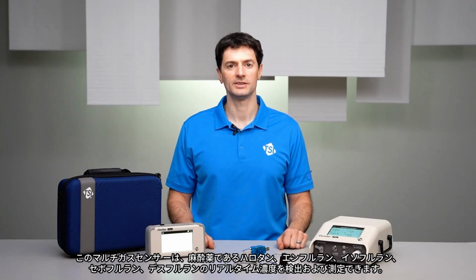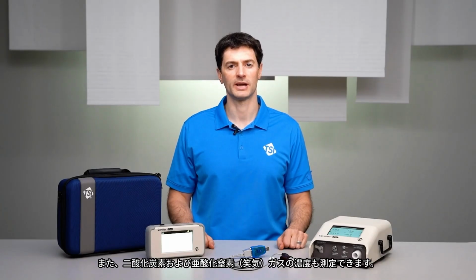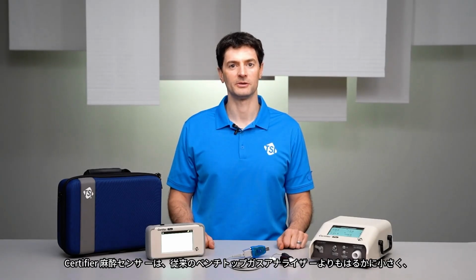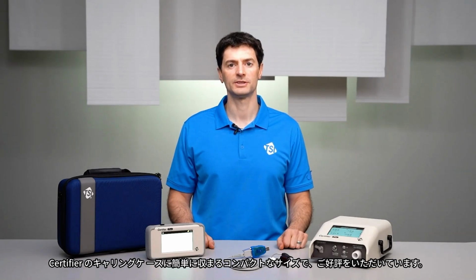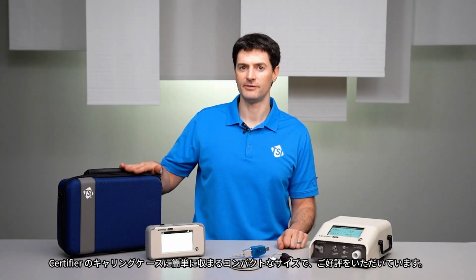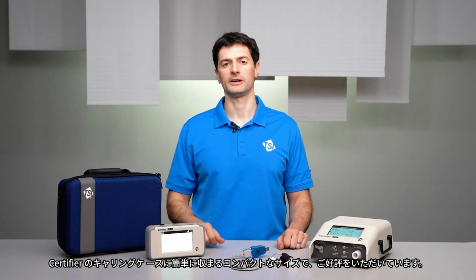This multi-gas sensor can detect and measure the real-time concentration of anesthetic agents halothane, enflurane, isoflurane, sevoflurane, and desflurane, as well as measure the concentration of carbon dioxide and nitrous oxide gas flows. Biomeds like the Certifier anesthesia sensor for its compact size, which is much smaller than traditional benchtop gas analyzers and can easily fit into your Certifier carrying case.